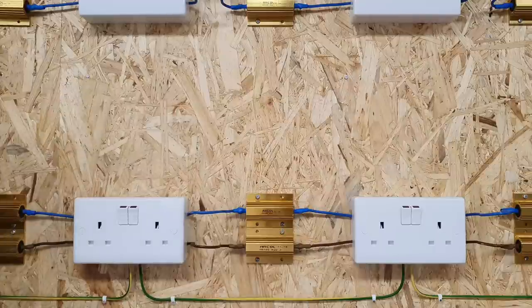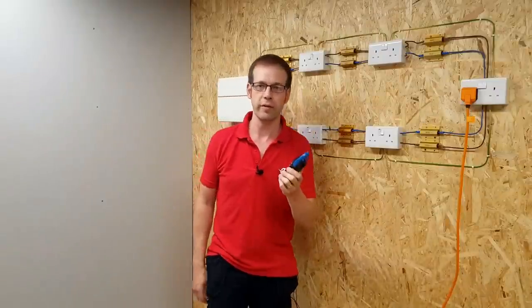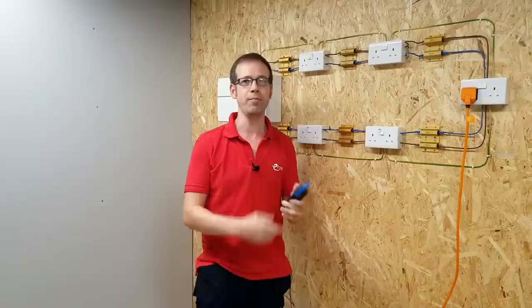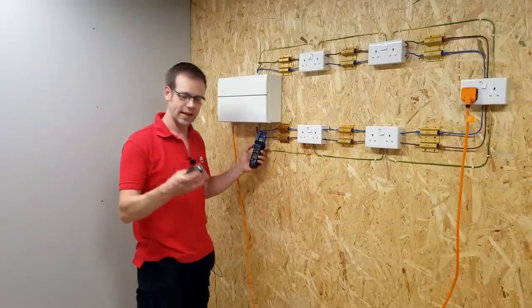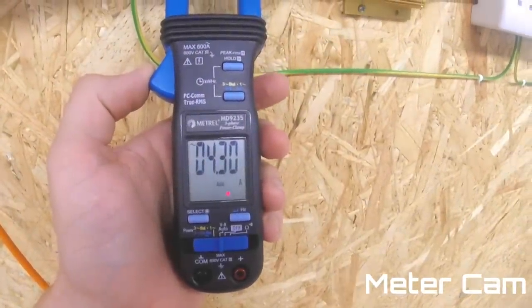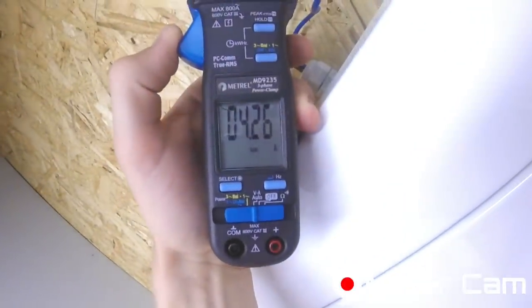We're going to use this rather lovely Metrel MD9235 to measure the current. It's capable of measuring power in unbalanced and balanced three-phase systems, but we're going to use one of its more basic features here and just measure the current flowing in each leg of the ring. At the bottom, we're measuring about 4.27 amperes — around 4.3 amperes. And on the top leg, we've got 4.2 amperes.